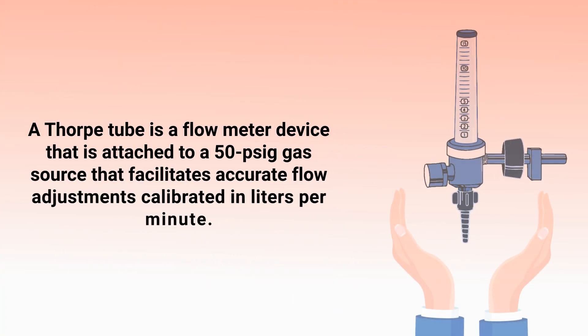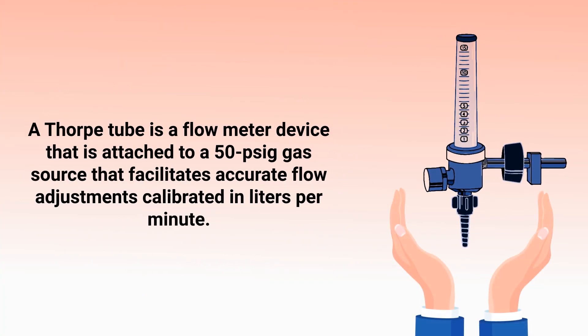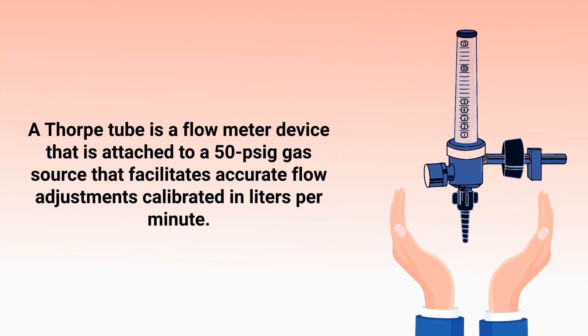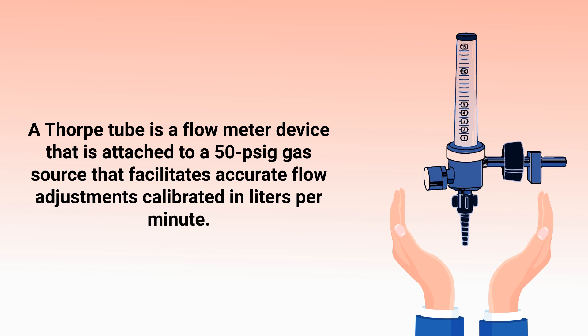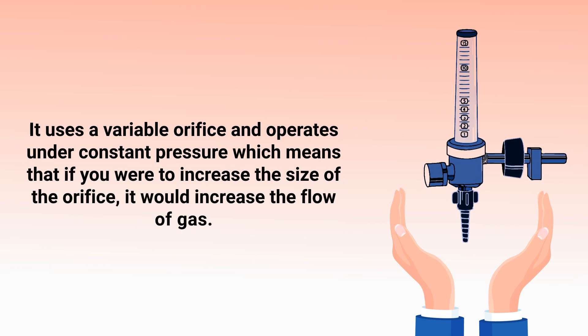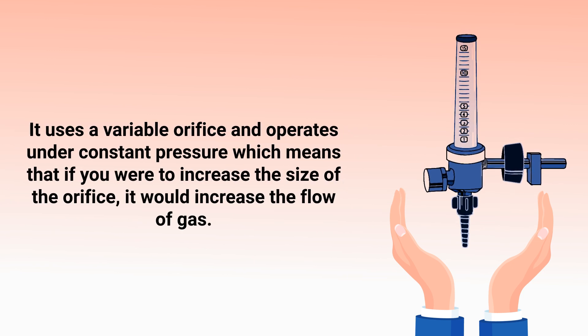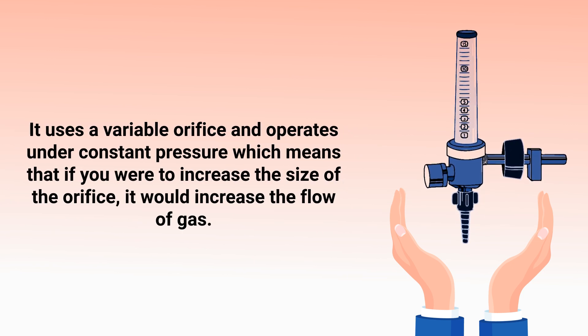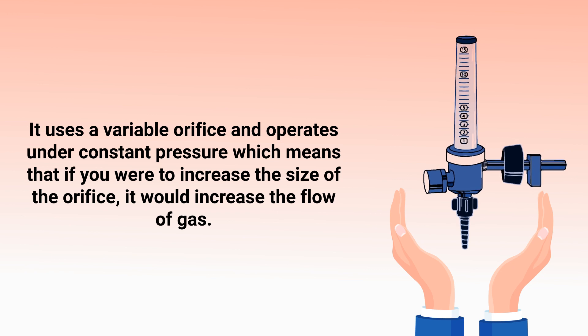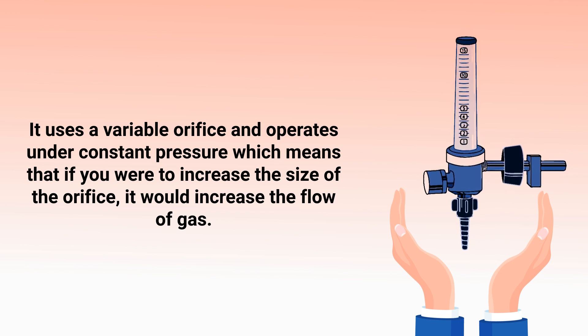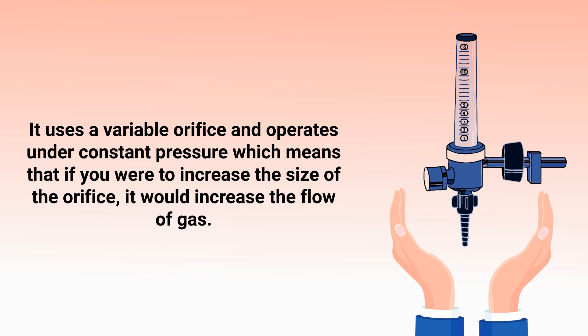A thorpe tube is a flow meter device that is attached to a 50 psig gas source that facilitates accurate flow adjustments calibrated in liters per minute. It uses a variable orifice and operates under constant pressure, which means that if you were to increase the size of the orifice, it would increase the flow of gas.